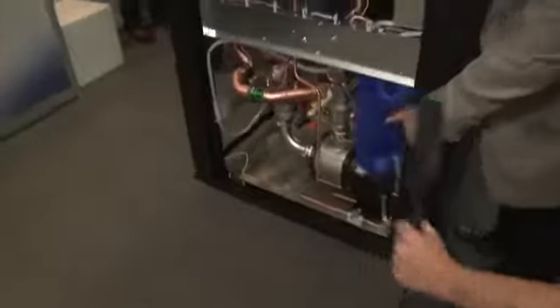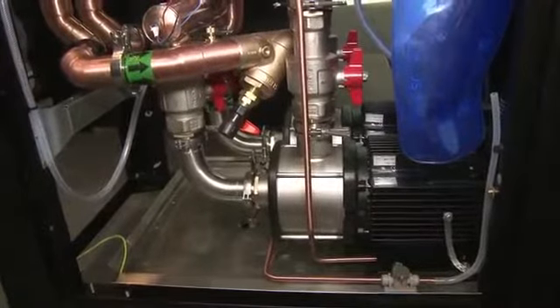It's the same sort of equation as before. If we have a look inside, the pumps are significantly larger. We've got dual redundant pumping capabilities — each pump does between 360 to 380 liters per minute. There's a fairly sophisticated control system built in such that every week you alternate between pumps, so that their service life is the same, and you're guaranteed that the backup pump isn't dried out or potentially not working when you need it the most.